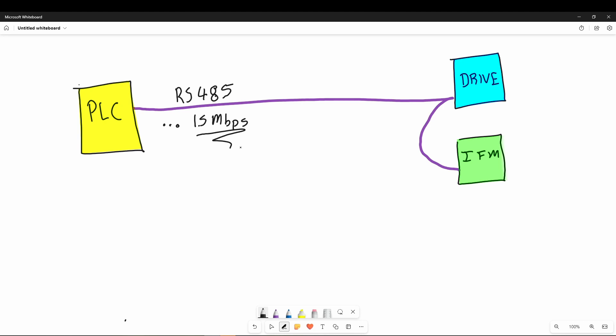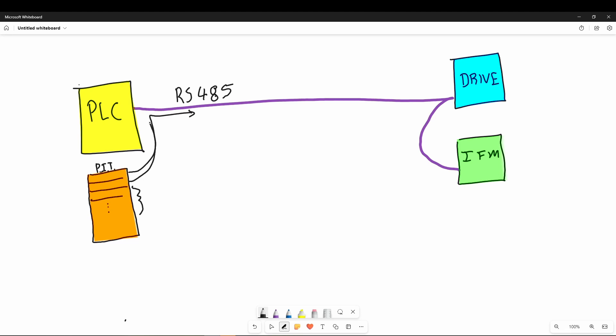If you are trying to send data across any network, you have to store the data somewhere while it waits to be sent. There is an area in a Siemens PLC called the Process Image Table where all data is stored and updated essentially once every cycle. This period changes based on the speed of the processor and the structure of the program. With serial communication like Profibus, the data lines up and a transmission starts, and one byte is transmitted at a time and is received across the bus. Now, the PLC, for reasons that we won't get into here, can only guarantee to be able to move two words in memory without something else going on and changing things.